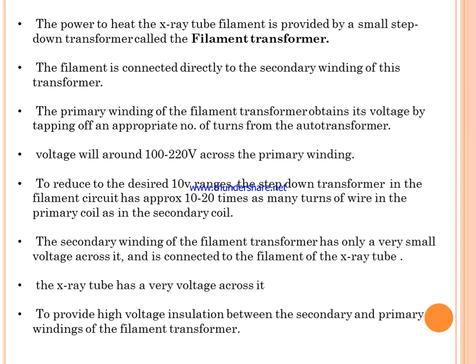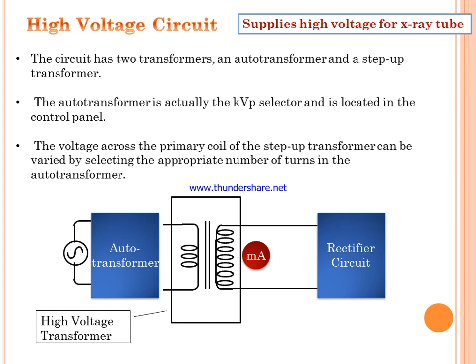The secondary winding of the filament transformer has only a very small voltage across it and is connected to the filament of the X-ray tube. The X-ray tube has a very high voltage across it, so high voltage insulation is provided between the secondary and primary winding of the filament transformer.